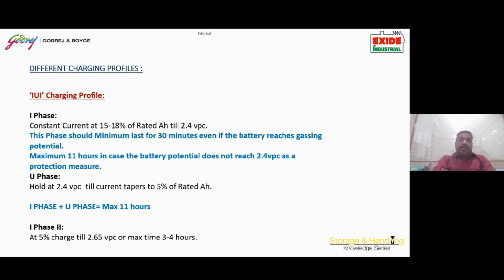However, the batteries need to be charged beyond 2.4 to achieve the full Ah capacity. So, how do we control this? If I continue to charge with a CC charger beyond 2.4, the constant current will continue to allow the hydrogen to escape at the same rate. So, the I phase lasts a maximum of 11 hours in case the battery potential does not reach 2.4 VPC, as a protection measure. The phase should last a minimum of 30 minutes even as the battery reaches gassing potential. So gassing potential is 2.4 VPC.